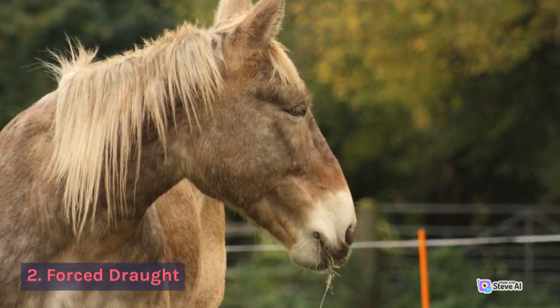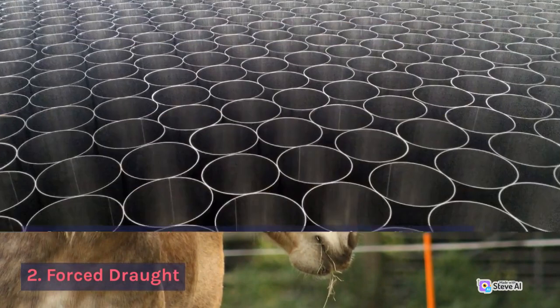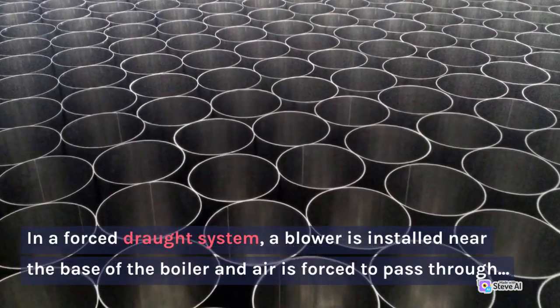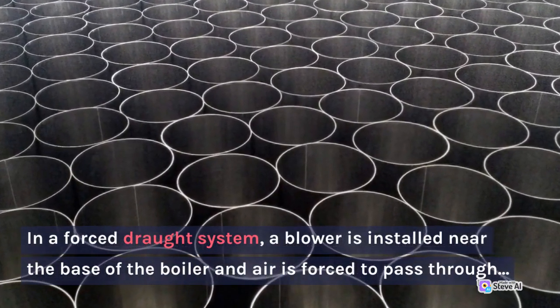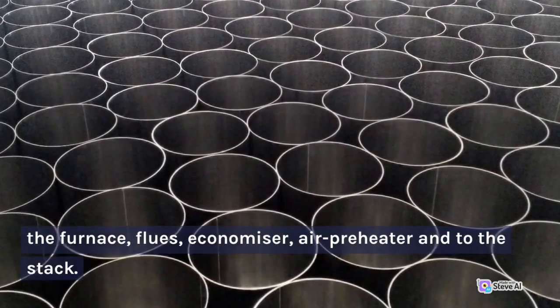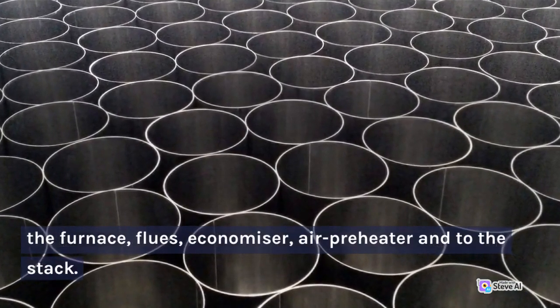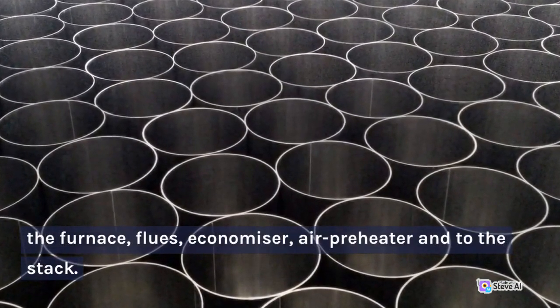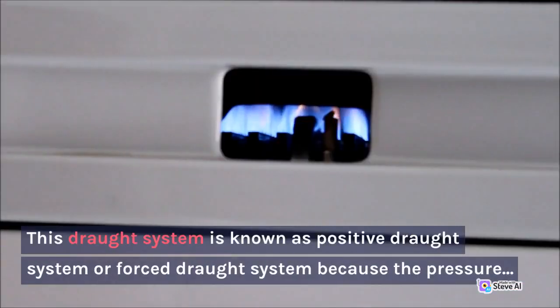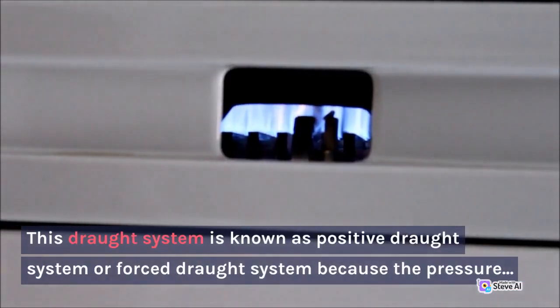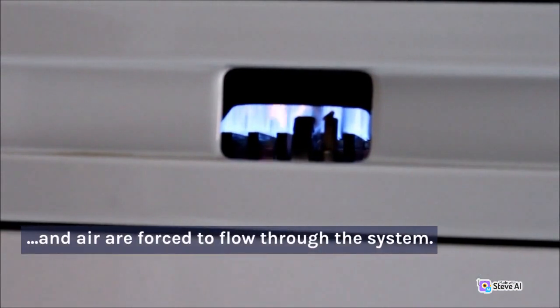2. Forced draft. In a forced draft system, a blower is installed near the base of the boiler and air is forced to pass through the furnace, flues, economizer, air preheater and to the stack. This draft system is known as positive draft system or forced draft system because the pressure and air are forced to flow through the system.